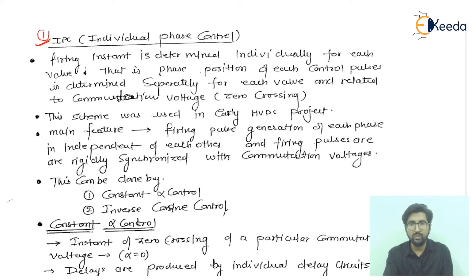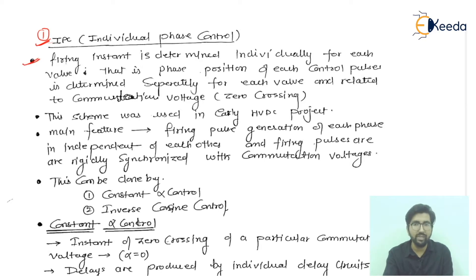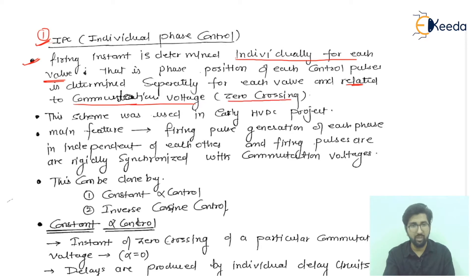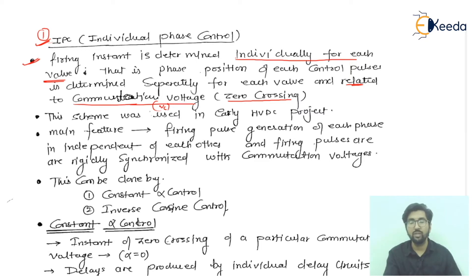Now we will talk about the IPC — Individual Phase Control. As the name suggests, we are individually controlling each and every phase. The first point is that the firing instant is determined individually for each valve, so we are using individual phase control. The phase position of each control pulse is determined separately for each valve and is related to the commutation voltage, which depends on the zero crossing. I will represent commutation voltage as Vc.